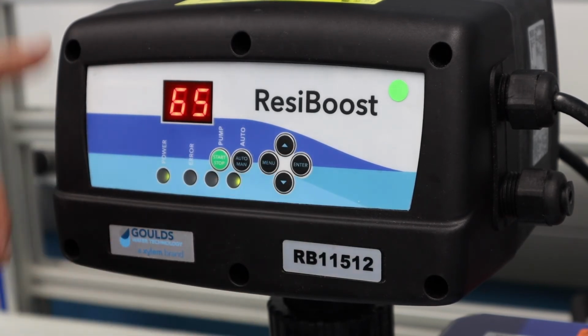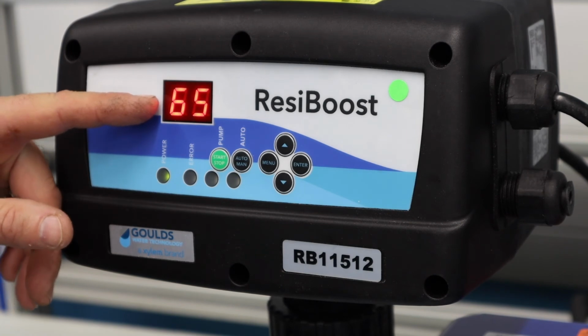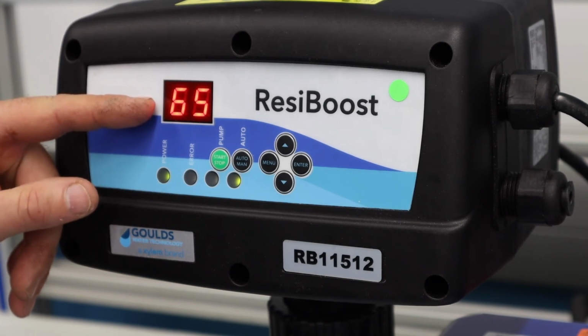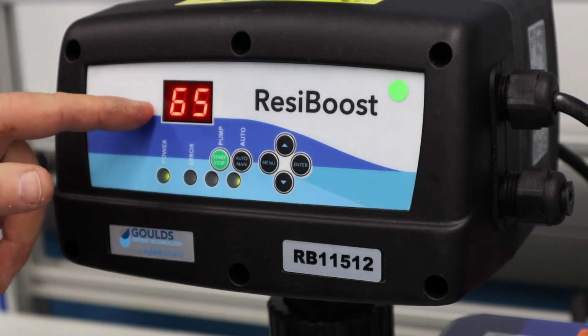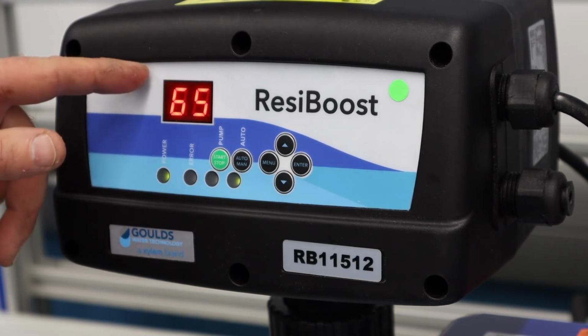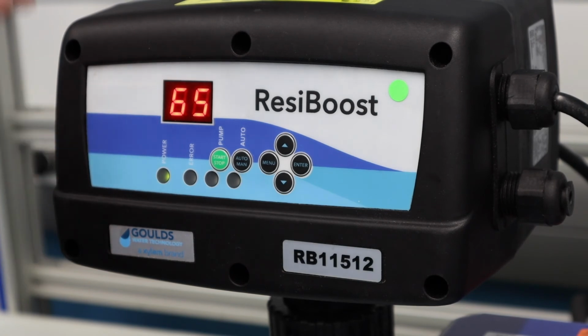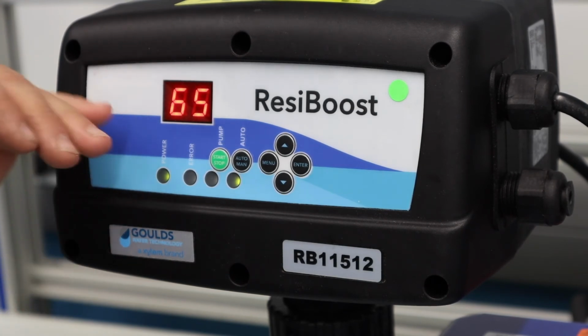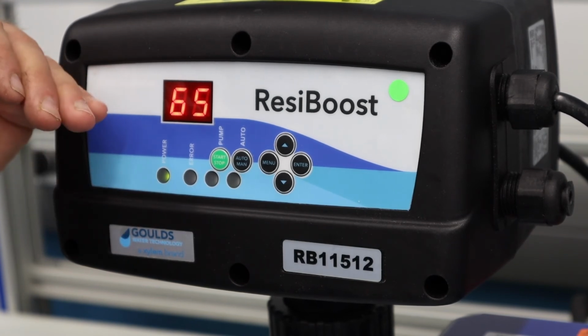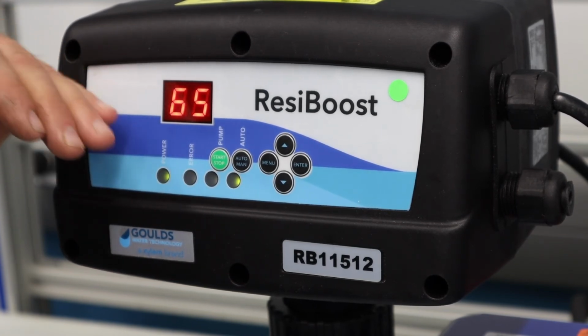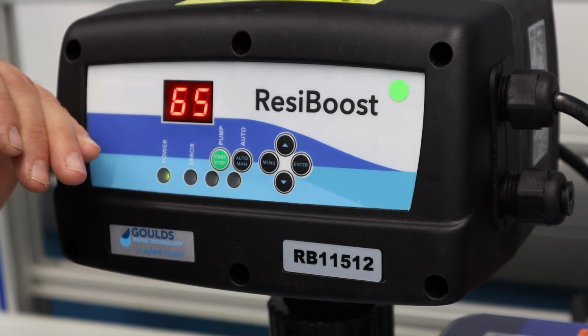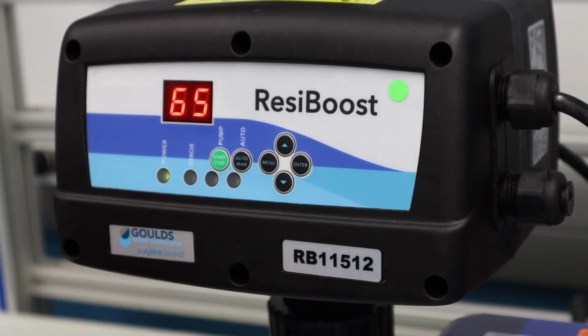The last parameter is DR, which is some more dry run protection. And this is, again, a percentage, and it's a percentage of the amperage, which was that first parameter. And so again, we got to do a little math here, but 65% of 10 is 6.5 amps. So if it gets below 6.5 amps, it is going to throw an A1 alarm. So it's more protection that you can modify, you can adjust, or you could just simply not use it. You can turn it off. So you got to hit the enter button when you're done. So now we're able to run. So that is it for the basic menu.